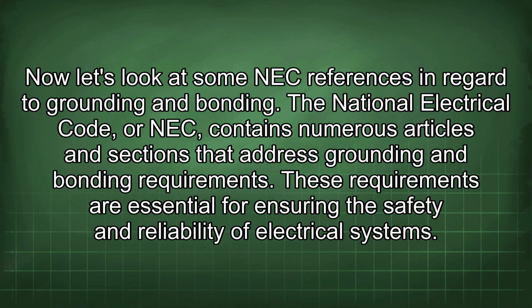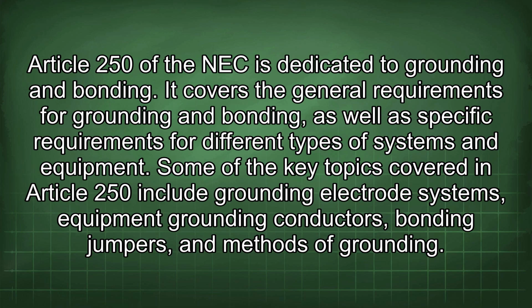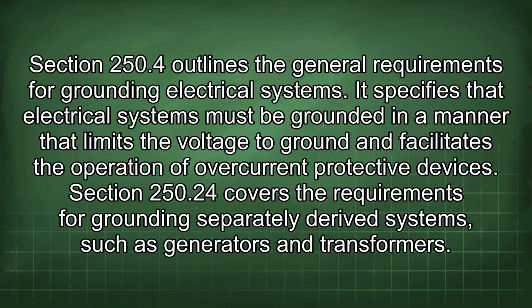The National Electrical Code, or NEC, contains numerous articles and sections that address grounding and bonding requirements. These requirements are essential for ensuring the safety and reliability of electrical systems. Article 250 of the NEC is dedicated to grounding and bonding. It covers the general requirements for grounding and bonding, as well as specific requirements for different types of systems and equipment. Some of the key topics covered in Article 250 include grounding electrode systems, equipment grounding conductors, bonding jumpers, and methods of grounding. Section 250.4 outlines the general requirements for grounding electrical systems. It specifies that electrical systems must be grounded in a manner that limits the voltage to ground and facilitates the operation of overcurrent protective devices.